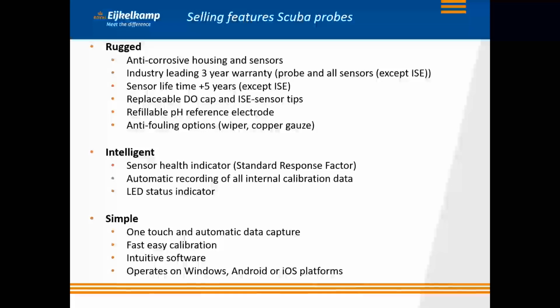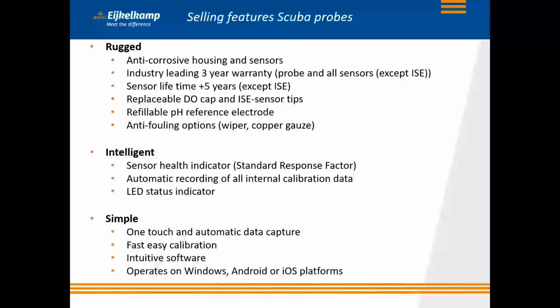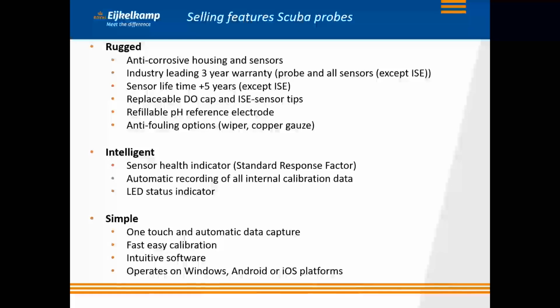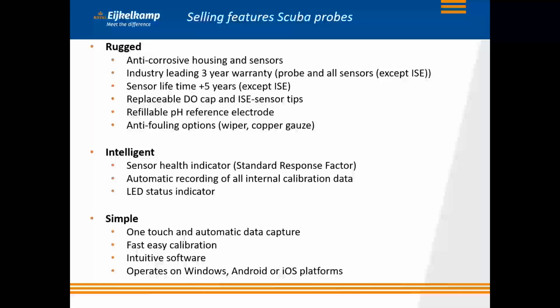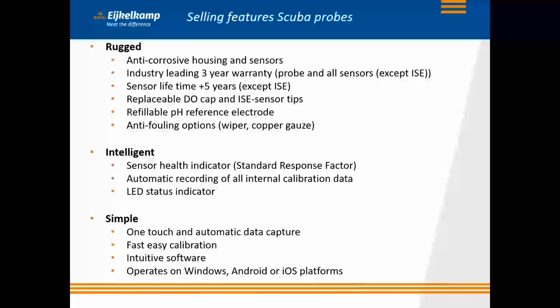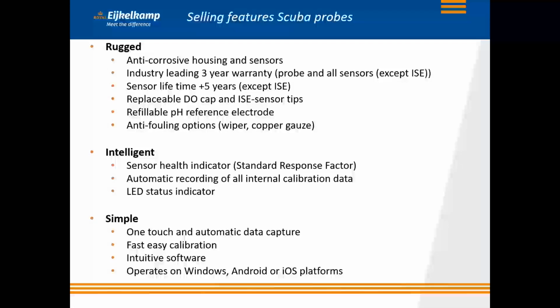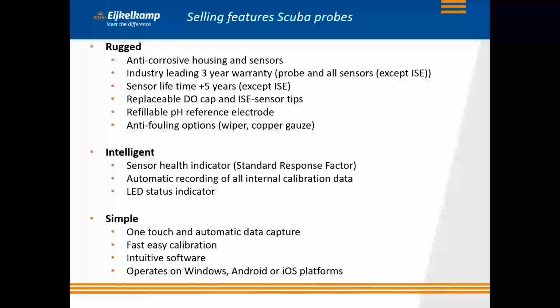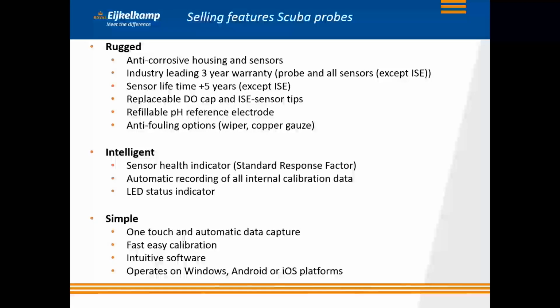They are also intelligent. And why? Because they have a sensor health indicator, and you can recognize that as a standard response factor during the calibration. From the main manufacturer, standard response is 100% or somewhat higher. And during the lifetime, the standard response factor can decline. So that gives you a better indication of the health of your sensor. Also, automatic recording of internal calibration data during the calibration, and it has an LED status indicator.